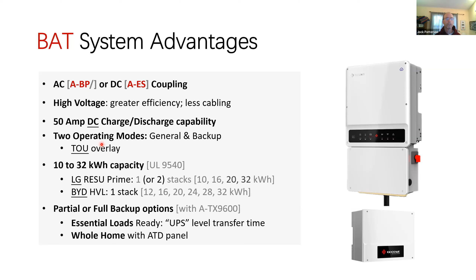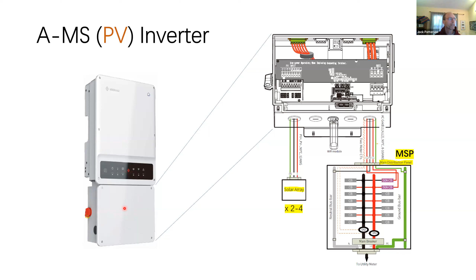But let's get on installation of a PV inverter. When you work on these inverters, you're only ever working in the wiring compartment here. The upper electronics box is just that. It's electronics. It comes from the factory for factory setting only. You're not going to work in that. If there's any problem in the upper wiring box, we RMA the unit, right? Your job is to do the wiring in the lower box.